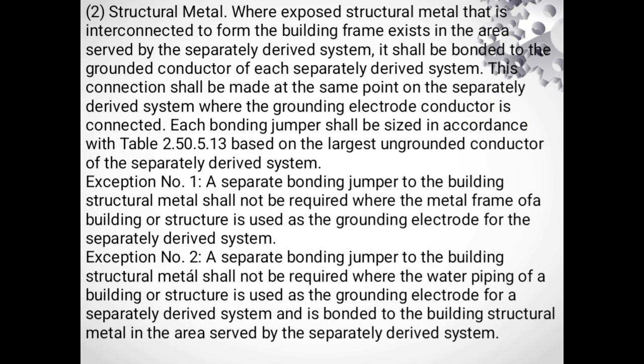Number 2. Structural metal. Where exposed structural metal that is interconnected to form the building frame exists in the area served by the separately derived system, it shall be bonded to the grounded conductor of each separately derived system. This connection shall be made at the same point on the separately derived system where the grounding electrode conductor is connected. Each bonding jumper shall be sized in accordance with Table 2.50.5.13 based on the largest ungrounded conductor of the separately derived system.